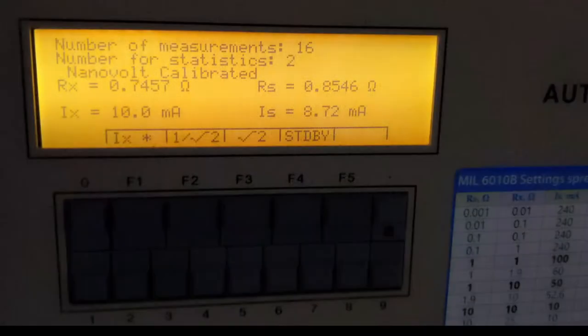Okay, go back to the stuff. So what I was describing on this picture was taken just a couple days ago when the bridge first failed after I power cycled it. It's actually supposed to show 1 ohm here and 1.9 ohm at RS.